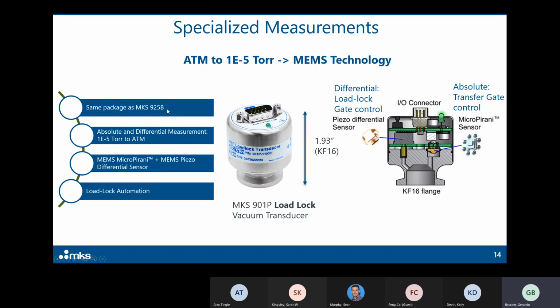This was the early stage, same package as the 925. This one does both absolute and differential measurement. It takes advantage of the micro-Pirani and also a MEMS piezo differential sensor. And this device is not only a pressure transducer, but also contains all the signal I/O that is required to control a load lock.